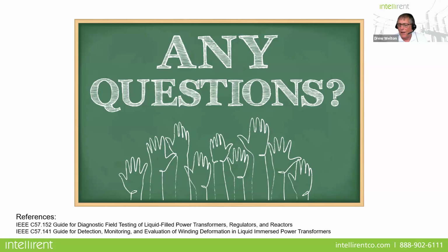We could have a whole other topic on what to do when you're commissioning a brand new transformer. You should always look for moisture and do dielectric frequency response. You should do a leakage reactance or short circuit impedance test to make sure that the impedance stamped on the transformer is true and accurate. You should do a DFR. There is a whole battery of commissioning tests that are very important, and a lot of that also helps you establish a baseline. On bushings, if you don't have a C2 standard or a C2 stamp on that bushing, I would definitely do a C2 test and establish that baseline. Okay.